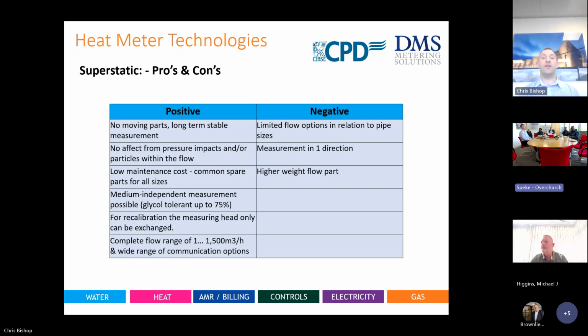Spare parts. Compared to what I said about the mechanical and the ultrasonics, if you were to, let's say, cut meters or damage cables on the static principle, the actual parts are available. So the cost conversation can be discussed. You can replace parts of that particular principle because it's not an ultrasonic design. It's a slightly different design that, weirdly enough, was designed by NASA back in the 60s, which is quite a common thing that I have to say during these CPDs. They used it on the space shuttles for the liquid nitrogen system. So that's how unique the measuring principle is, and you could say it has been around for about 50, 60 years.